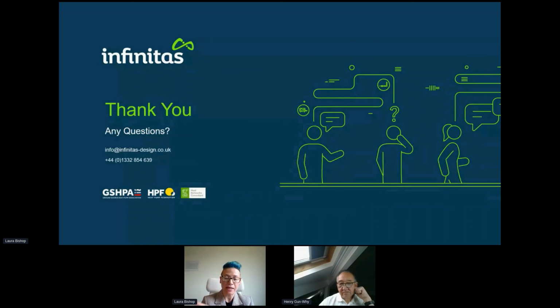You can use the BMS to turn it on and off on a time clock basis, but not to operate the heat pump. I wouldn't recommend that. Let the heat pump do its own thing using its own inbuilt temperature or pressure sensors, however you want to control it. The heat pump will also control its own brine temperatures, so pumping is variable speed depending on what the heat pump is doing at any one time. But yes, incorporating the heat pump control system with the BMS is critical to success and to efficient running.